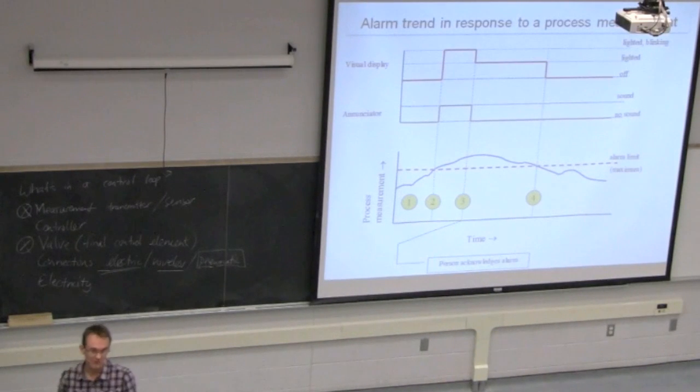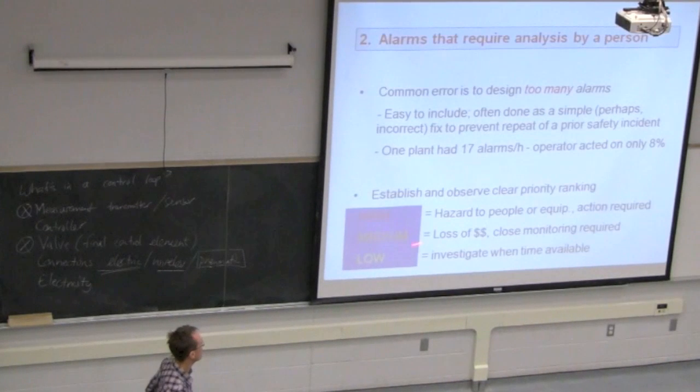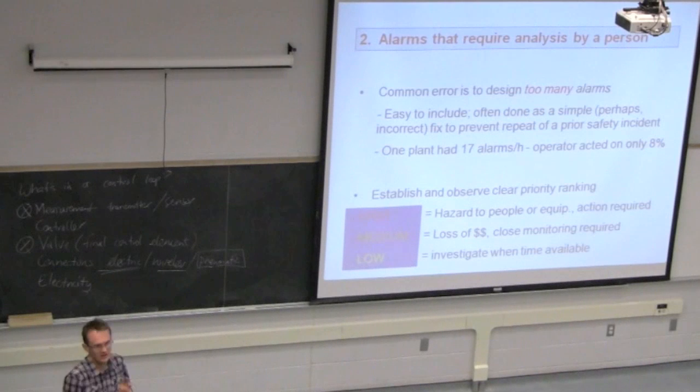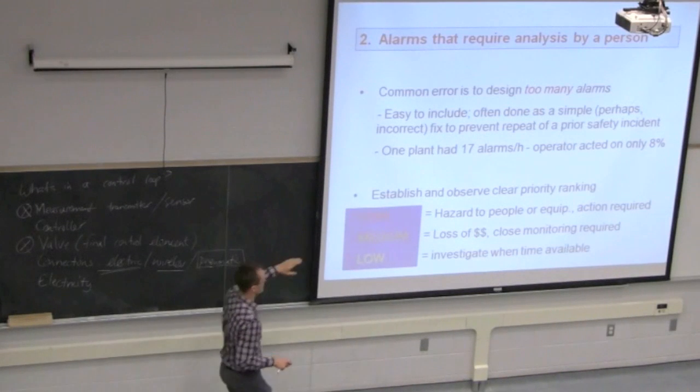Multiply this by 500 potential alarm circuits on a company's system. There's a potential for many alarms per hour. Okay, so what we do is that we classify alarms into low, medium, and high priority so that the operator can know where to address their attention. Should two or three alarms occur simultaneously, and that's fairly typical, right? If a problem happens, the temperature exceeds, the pressure probably also exceeds, so two things could be going on. We have ranked them as low priority, medium priority, and high priority.